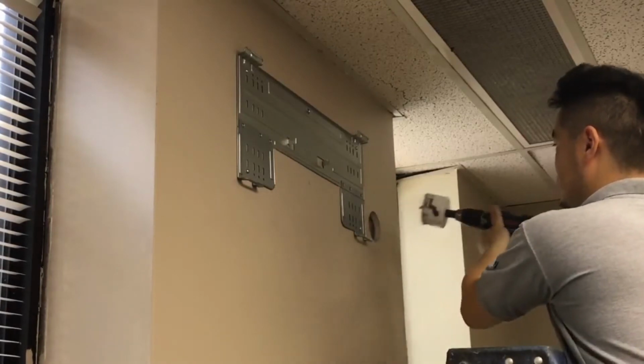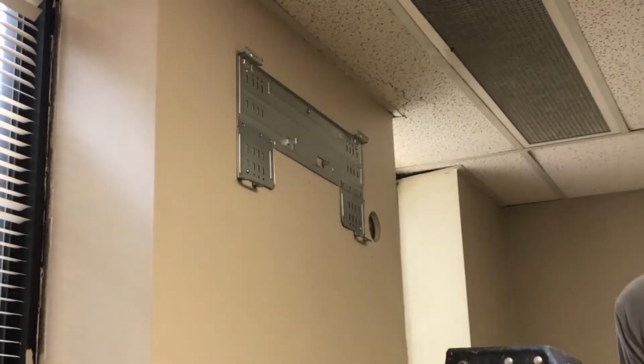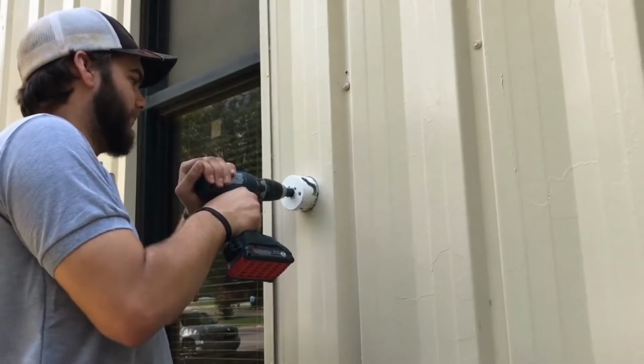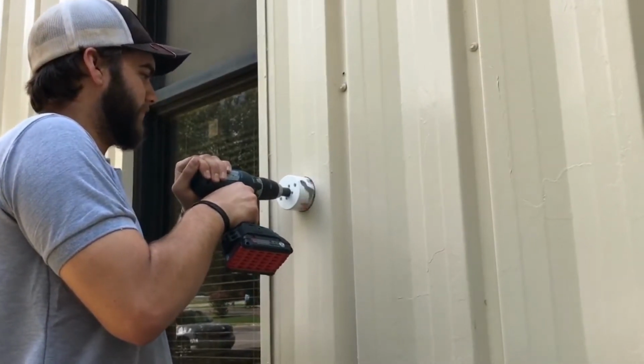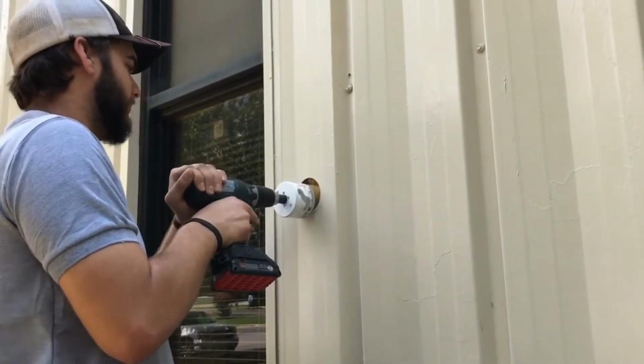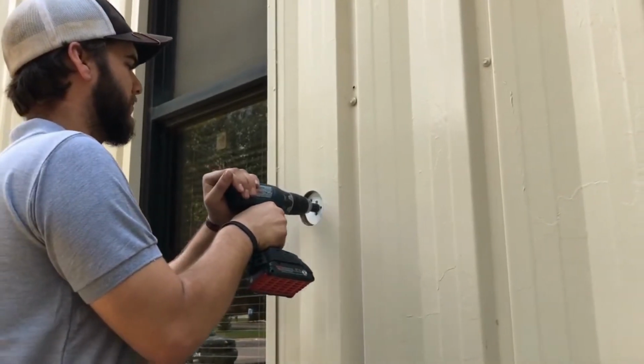Now you will create a hole in the wall to allow refrigerant lines, control wires, and condensation drain tube to go outside. The hole is usually 2.5 to 3 inches. Using a hole saw bit, drill the hole, making sure to angle downward to the outside for proper condensate drainage.